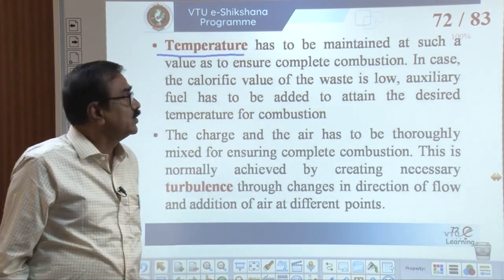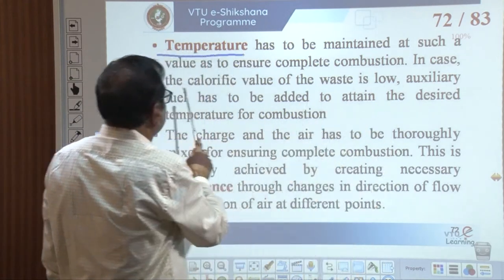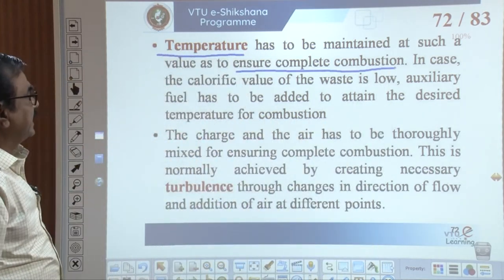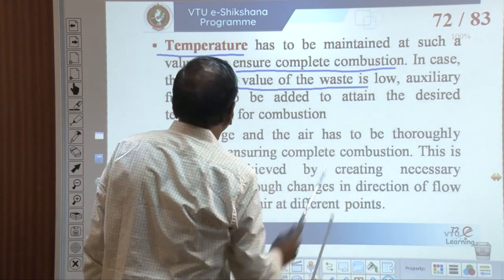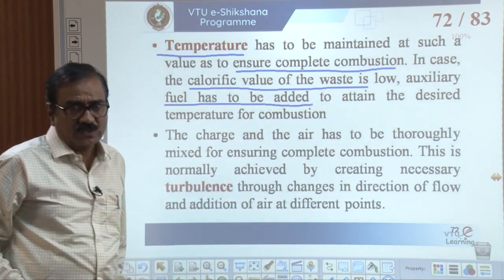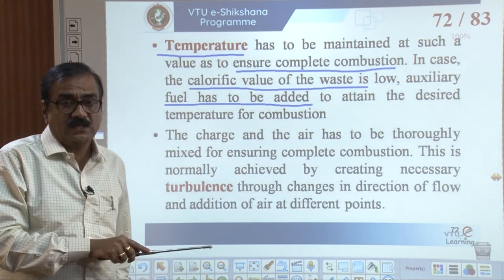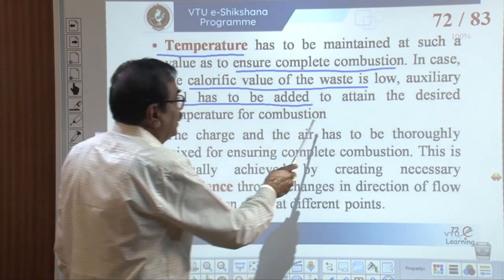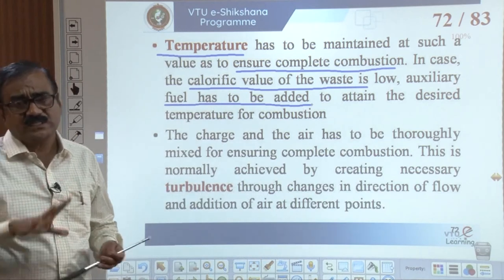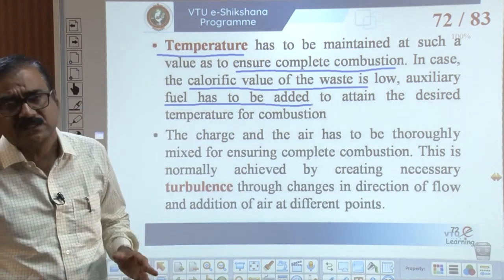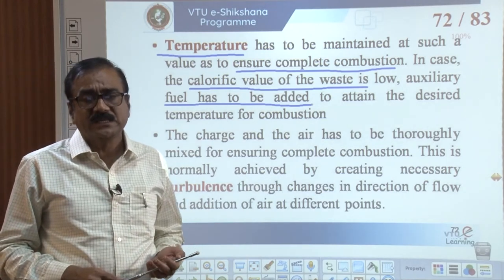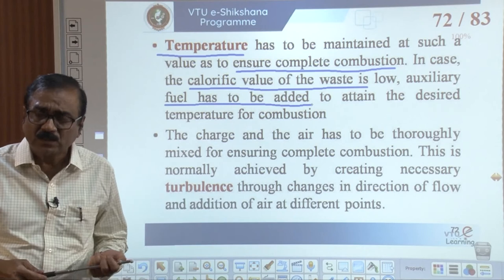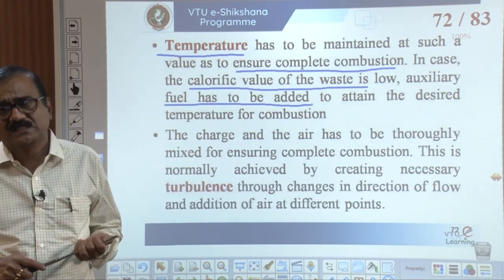By and large from experience, it is found that approximately around 900 degrees Celsius — not less than 870 degrees Celsius — temperature should be maintained in the incinerator so that burning takes place efficiently. To attain the desired temperature, if the calorific value is insufficient, auxiliary fuel is needed.